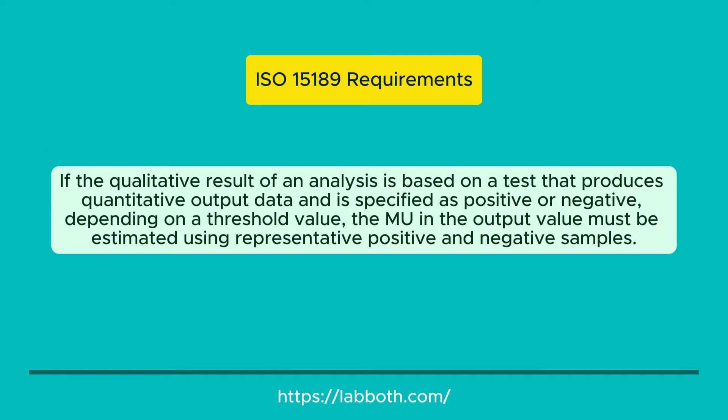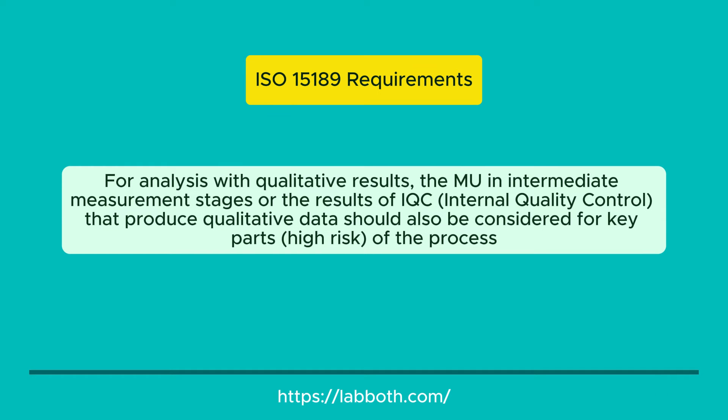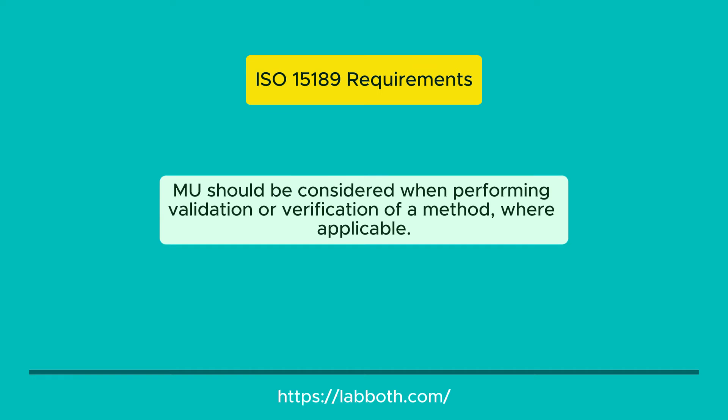When users inquire about MU, the laboratory's response must consider other sources of uncertainty, such as biological variation. If the qualitative result of an analysis is based on a test that produces quantitative output data specified as positive or negative depending on a threshold value, the MU in the output value must be estimated using representative positive and negative samples. For analyses with qualitative results, the MU in intermediate measurement stages or the results of IQC (internal quality control) that produce qualitative data should also be considered for key, high-risk parts of the process. MU should be considered when performing validation or verification of a method, where applicable.